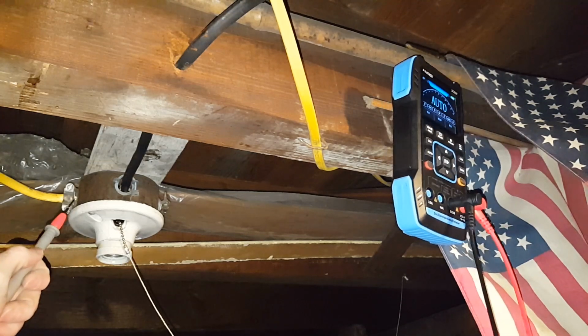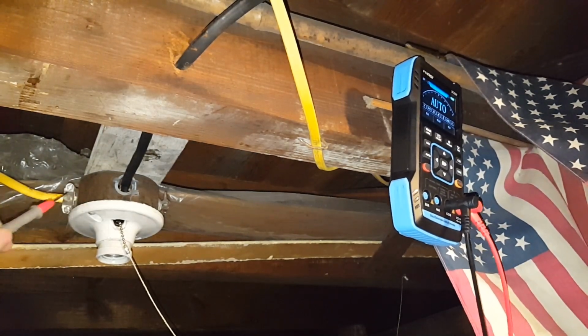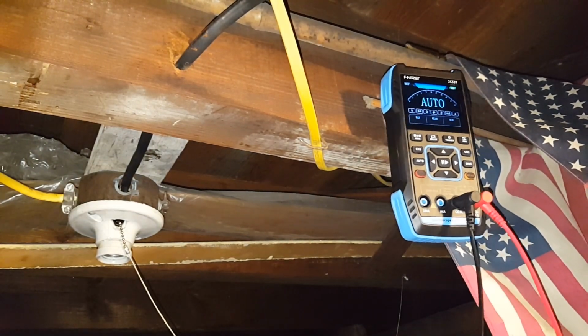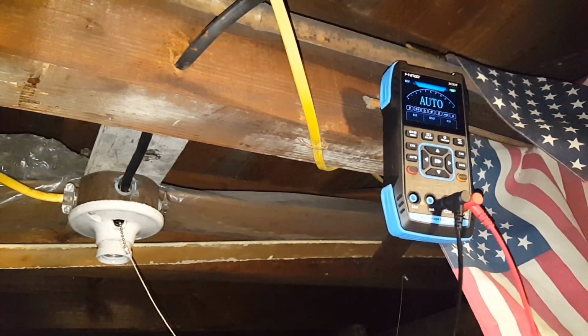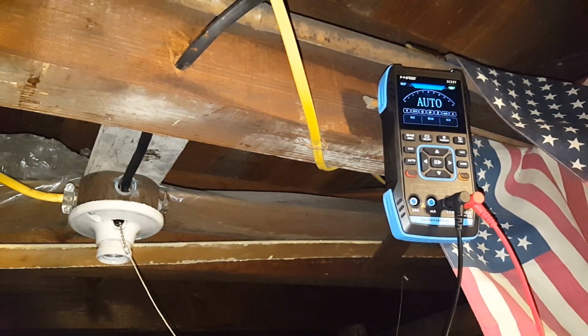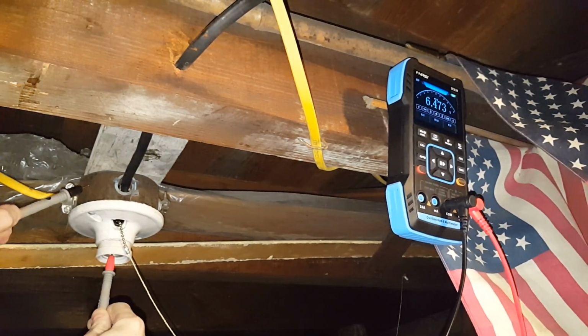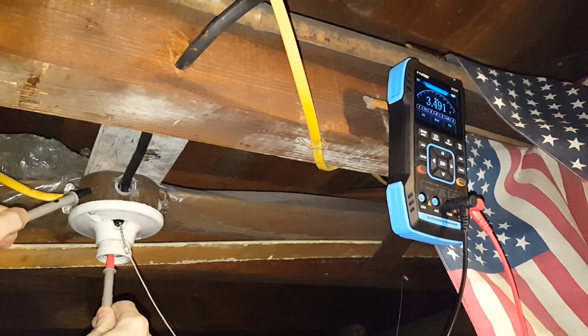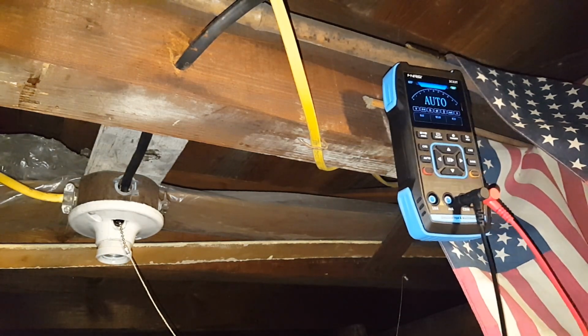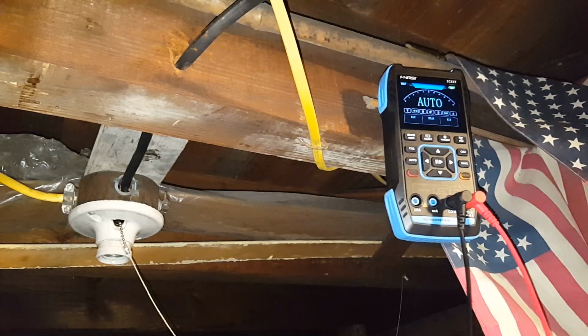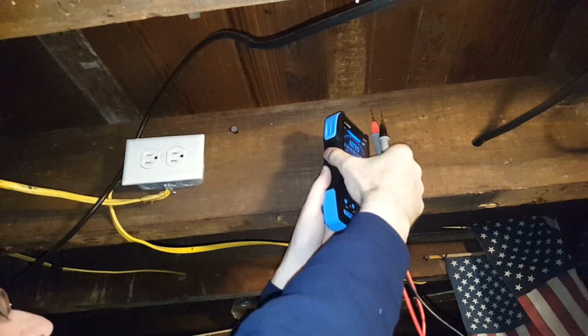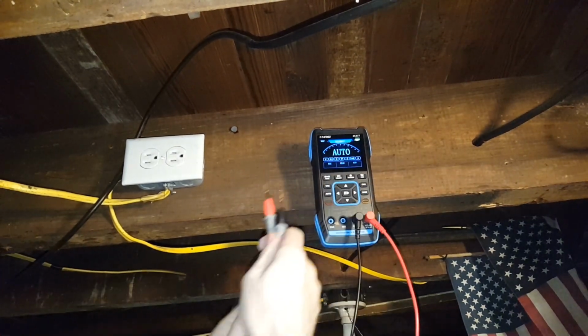To see if something is grounded, this metal should be grounded. So I should be able to send 120 volts through the metal back through the ground. And it does not. That tells me that this is not grounded. So I know that metal in there does not have a ground going to a ground screw. Outlet, a receptacle. It's on auto again.